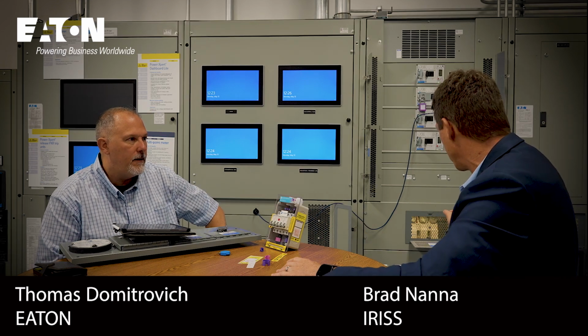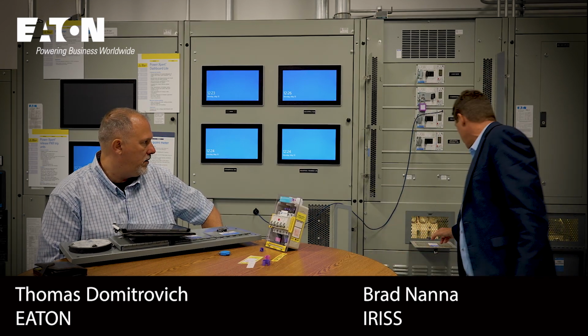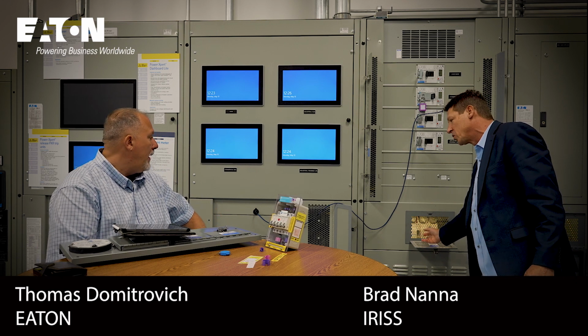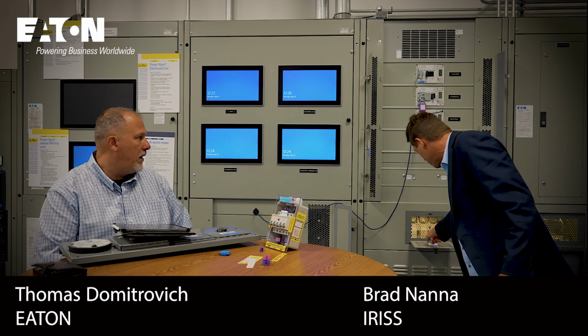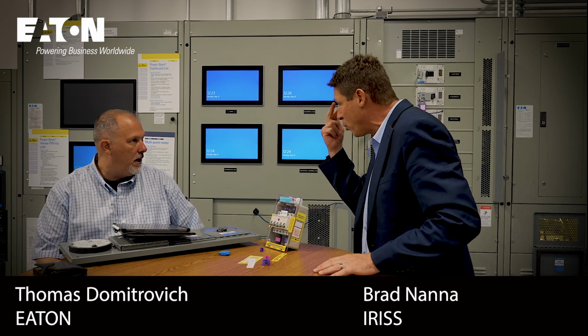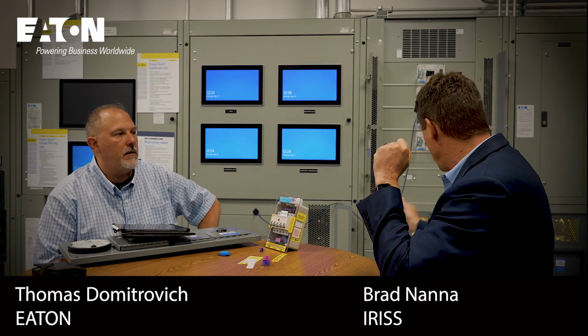What we have is a sensor—maybe you can't see it here—there's a port that you plug an ultrasound device into. Now I'm able to hear, through a sensor back there, before I can even see it. This is only done when performing a test. That sensor lets me hear the arcing, the tracking, the treeing, which leads up to a partial discharge situation, the corona.